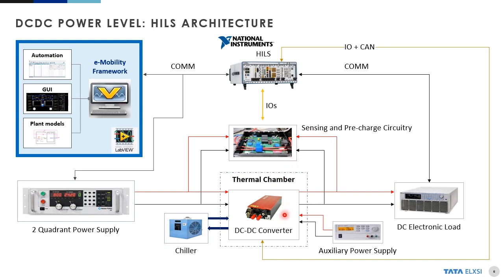The device under test is kept inside a thermal chamber and connected to a chiller for validating functionalities related to temperature, like temperature derating functionality. All the programmable devices, the device under test as well as the sensing and pre-charge circuitry is controlled and monitored by the real-time HILS using e-mobility framework.